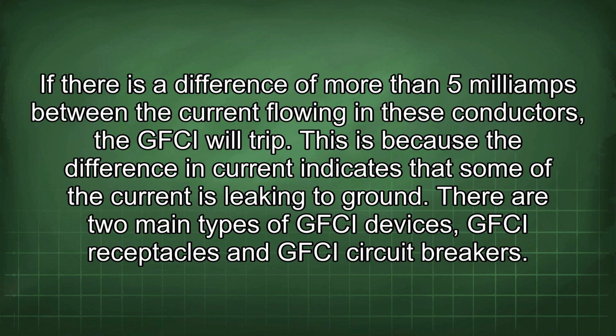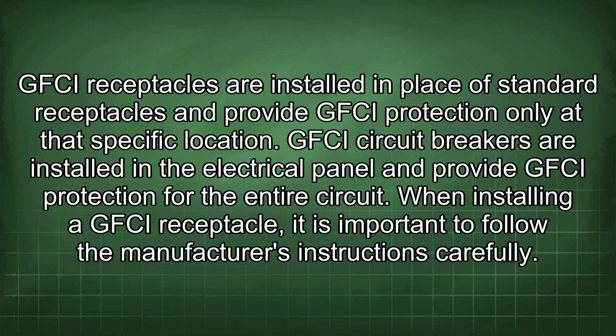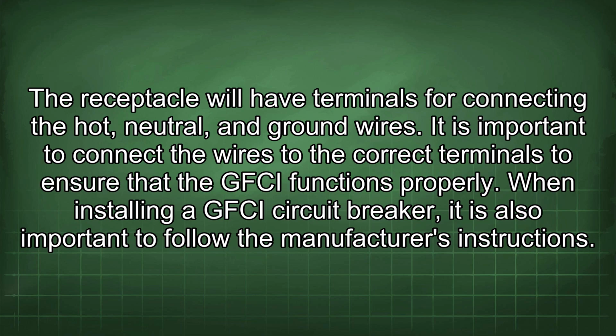There are two main types of GFCI devices: GFCI receptacles and GFCI circuit breakers. GFCI receptacles are installed in place of standard receptacles and provide GFCI protection only at that specific location. GFCI circuit breakers are installed in the electrical panel and provide GFCI protection for the entire circuit. When installing a GFCI receptacle, it is important to follow the manufacturer's instructions carefully. The receptacle will have terminals for connecting the hot, neutral, and ground wires. It is important to connect the wires to the correct terminals to ensure that the GFCI functions properly.